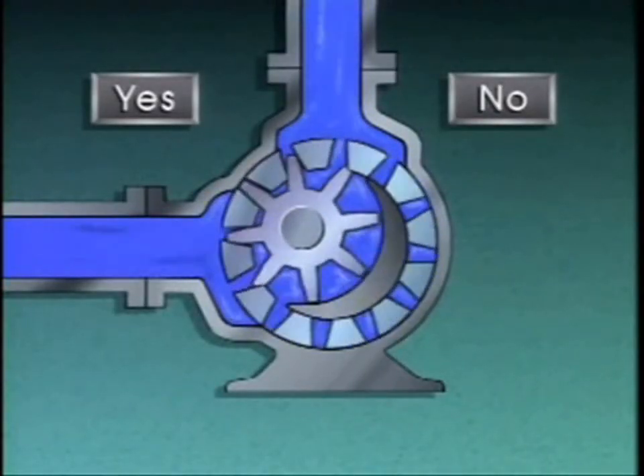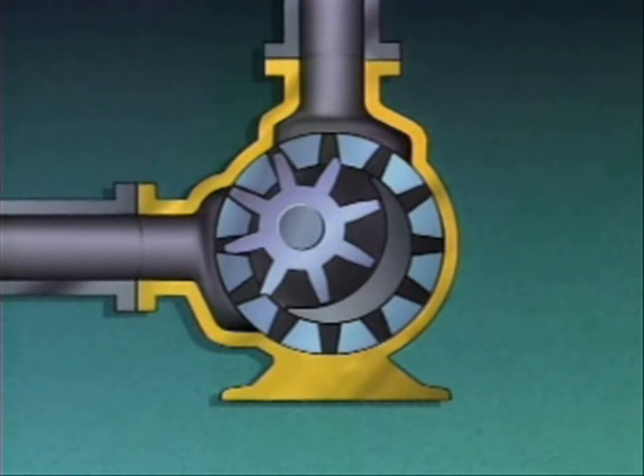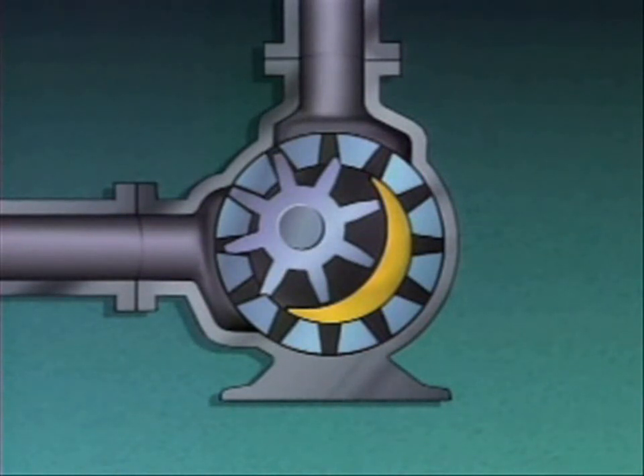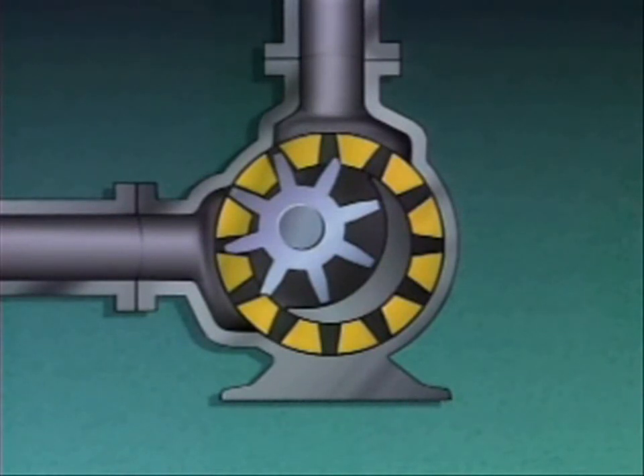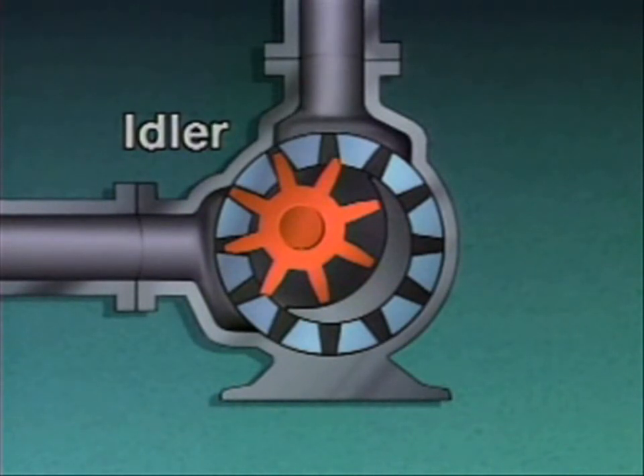This is an internal gear pump. This pump has a casing with a suction port and a discharge port. Inside the casing are a crescent-shaped spacer and two gears. The spacer prevents liquid from flowing from the discharge back to the suction of the pump. On this pump, the outside gear is rotated by the pump's driver, so it's the power or driver gear. The inside gear moves because its teeth are meshed with the teeth of the driver gear, so it's the idler gear. But keep in mind that on some internal gear pumps, the inside gear is the driver and the outside gear is the idler.